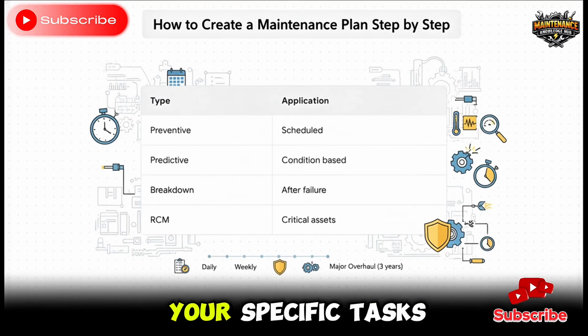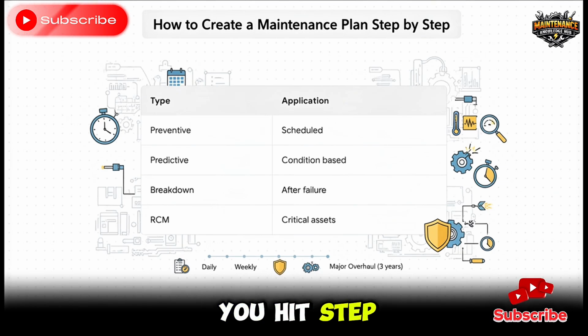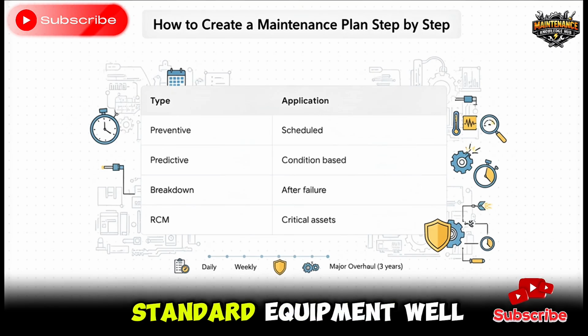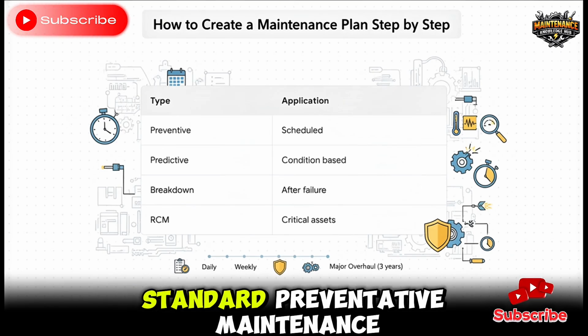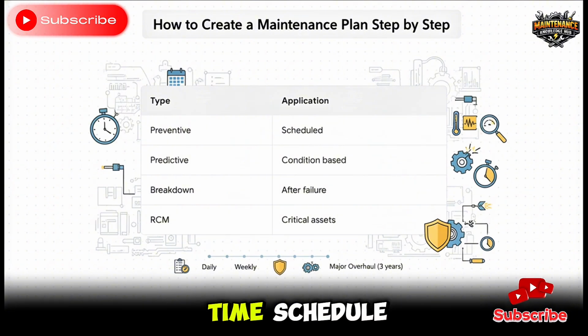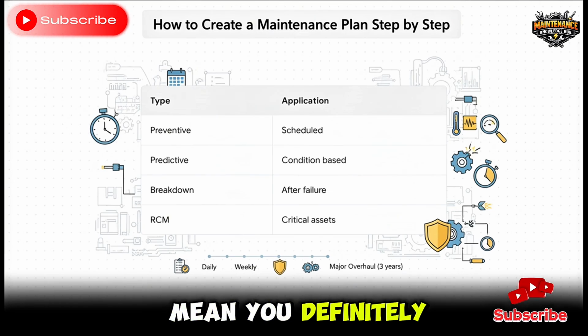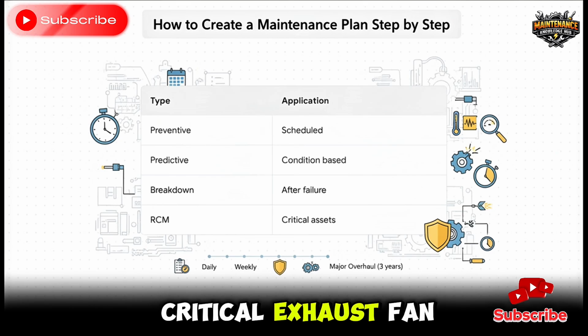Once you've identified your specific tasks, you hit Step 5, decide maintenance strategy. Think of this as a giant decision matrix. If you've got standard equipment, well, you might just do standard preventative maintenance based on a strict time schedule. But if you're dealing with your heavy hitters, your critical assets, then you strictly apply a strategy like reliability-centered maintenance. You definitely don't apply RCM to a non-critical exhaust fan, right?